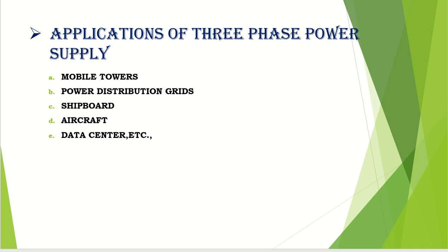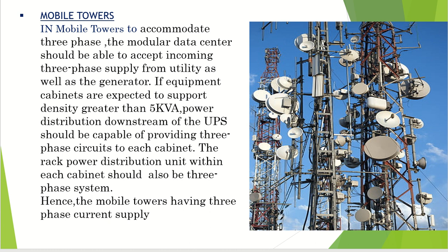If equipment cabinets are expected to support density greater than 5 kilovolt-amperes, power distribution downstream of the UPS should be capable of providing three-phase circuits to each cabinet. The rack power distribution unit within each cabinet should also be a three-phase system. Hence, the mobile towers have three-phase power supply.